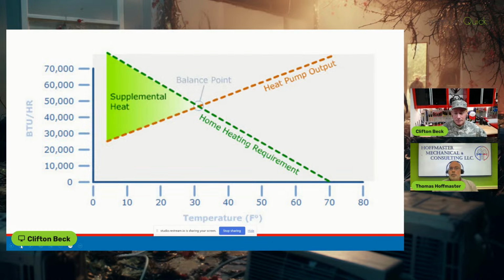What I've run into for years and years is that you're usually called in because people are selling heat pumps, selling expectations they can't manage, and that haven't even been determined with a load calculation. That's what's critical when we look at load calculations and the capability of heat pumps, because when we start comparing heat pumps, they do not all perform the same, so it's very important to know what those capabilities are.